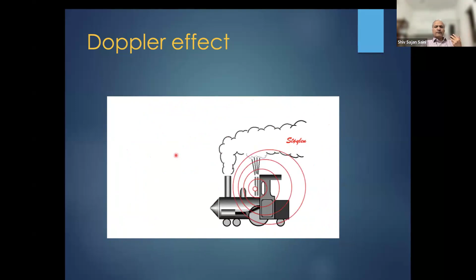So how do we scientifically understand what the Doppler shift is, and its principle and its application? This is a schematic diagram. This is an RBC and this is the ultrasound probe. Now the probe is going to throw a beam. It is going to strike, and there is a certain energy and a certain frequency associated with it. The transmitted beam has a frequency, which we depict as Ft. That is the frequency of the transmitted beam. Now it is going to hit and come back, and this is the reflected frequency.